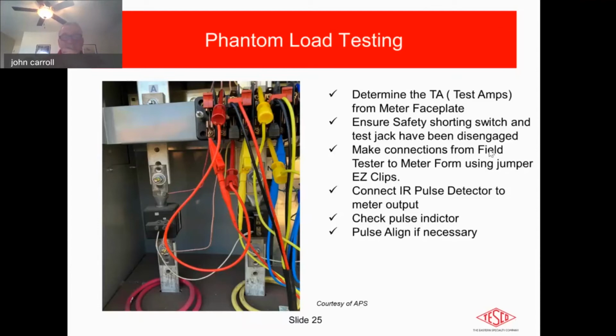Okay, thanks, John. Okay, so phantom load testing. This idea, of course, is now to control delivery of the load as opposed to the customer's load. And you can see here, it's difficult to get a clear photograph because I don't want to get too close. But what I'm showing you here really is the connections with this little red EZ clip. These are also on the actual current on the test switch. And you can see down here, the duckbill is in place.